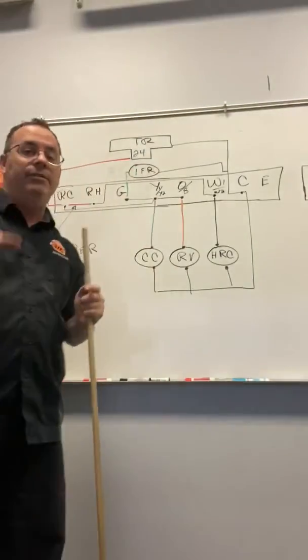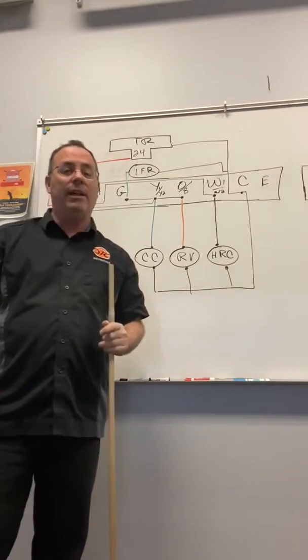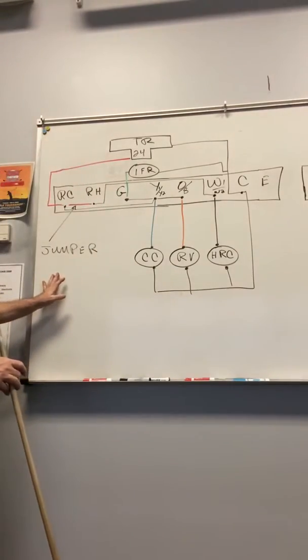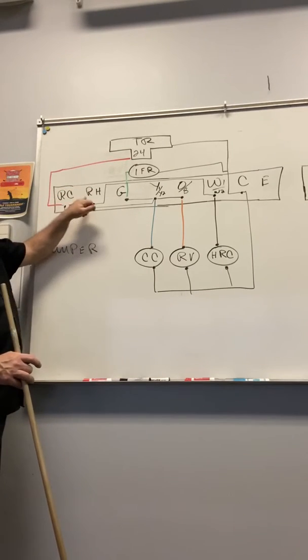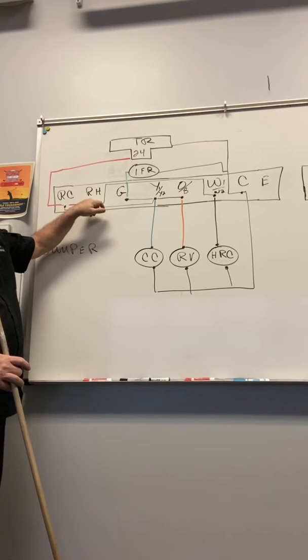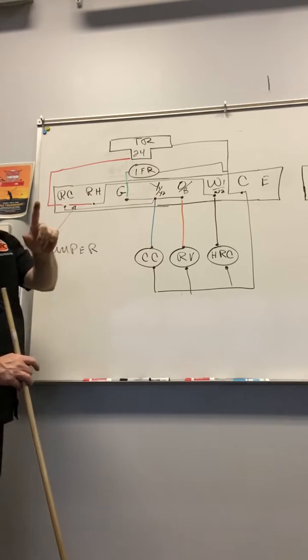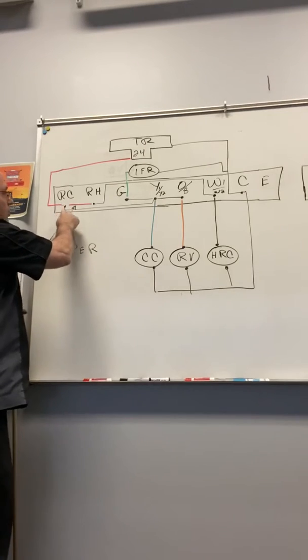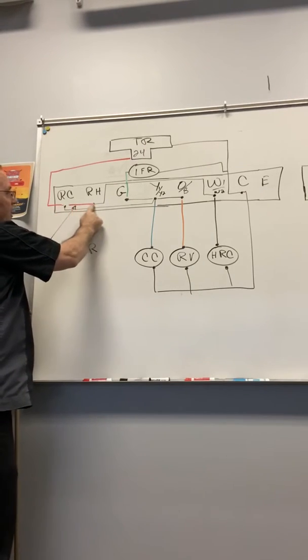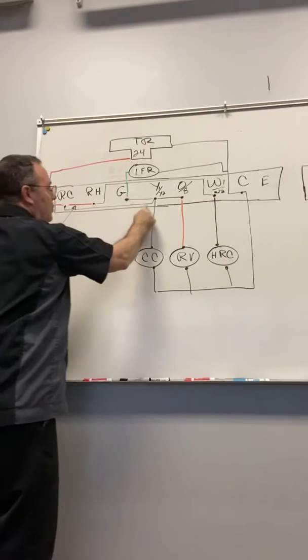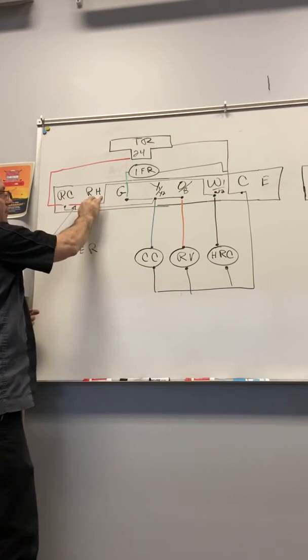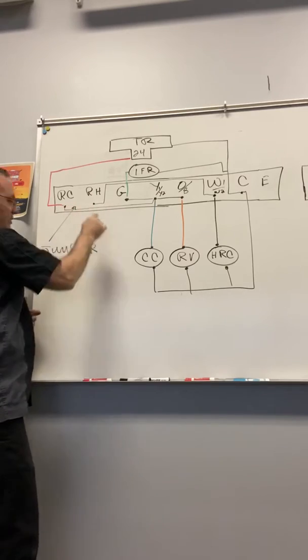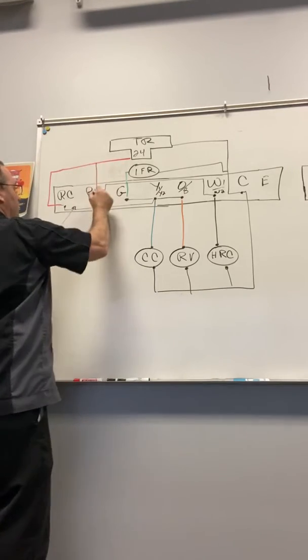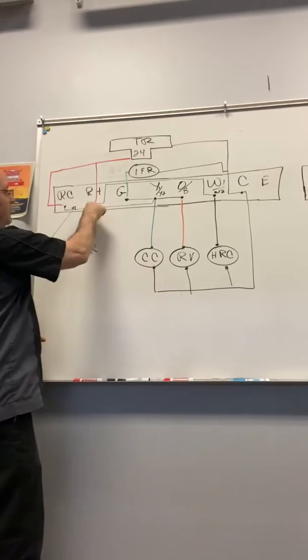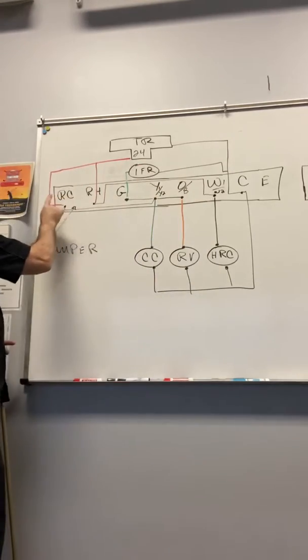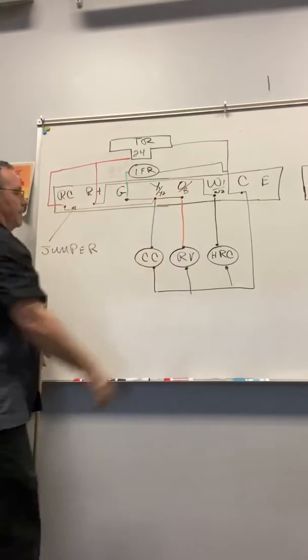Now, I will give you handouts when you come back to class explaining all that in detail so you can bring it in the field. So notice RC and RH here are normally not connected. But when you buy the thermostat, you'll notice there's a red wire jumper in there. Well, that's sending power to heat and to cool, depending on which one's selected. So in actuality, R is connected to both of these. If your thermostat picks heat, it sends the power that way. If it picks cool, it sends the power to the cooling side.